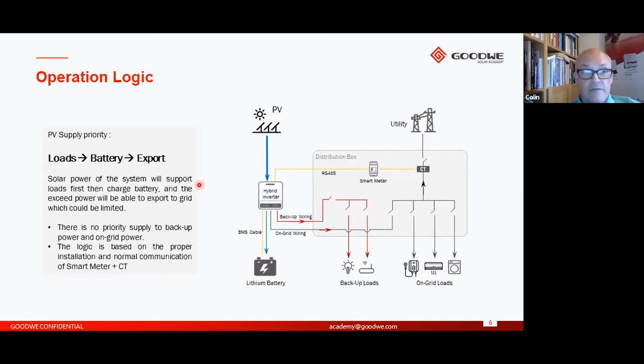Okay, so let's now look at the other side of the coin, where perhaps it's a very poor PV day and we're only generating, again, let's say 500 watts. And let's say that the building demand is, just as an example, 3 kilowatts of energy. So we're not producing very much power here, but because we know we need some extra power, this inverter will detect that, and if there is the capacity within the battery to be able to discharge to help support the loads, then it's going to do that.